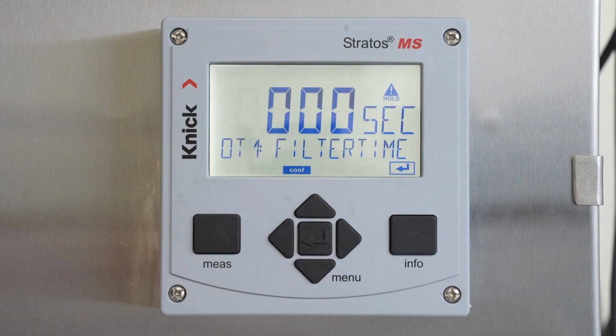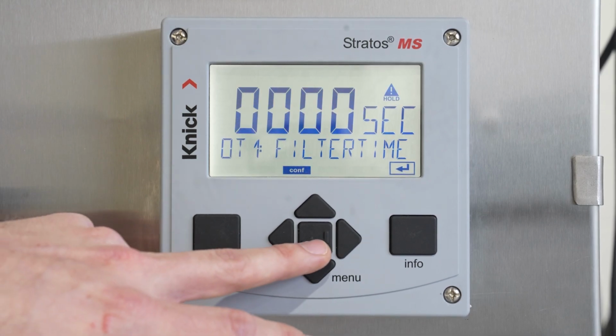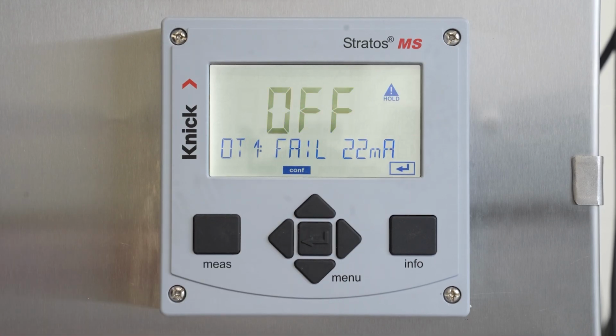Here, you will see our filter time. This is also referred to as dampening, which allows us to smooth out any peaks and valleys in our 4 to 20 milliamp output. We will leave it set to the default of 0 seconds. Lastly, we have our failure mode. This determines what we want the milliamp output to do when we are in failure of our Stratos MS device. By turning this on, we can drive the milliamp value to 22 milliamps in the event of a failure. We can do the same when our Memosens Sensoface icon turns to a frown.